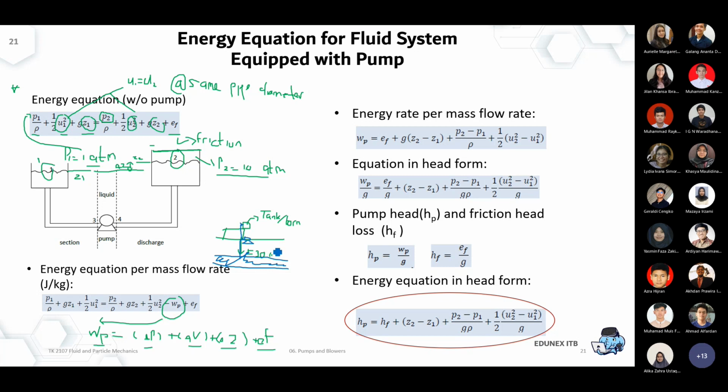Let's say I drill a well of 30 meters and then I have another elevation, depending on your house. If it's one level, maybe it's only 5 meters, for example. But if it's a 2 story home, maybe it's 10 meters. Just a quick comparison, let's say 5 to 10 meters. So now in total, the pump has to provide the delta elevation for, let's say, 40 meters. That's very common.